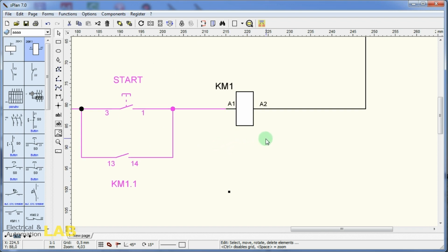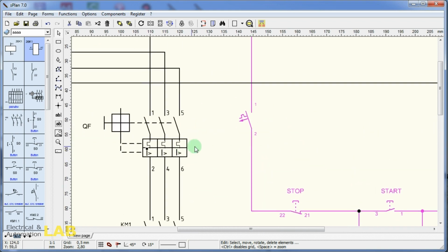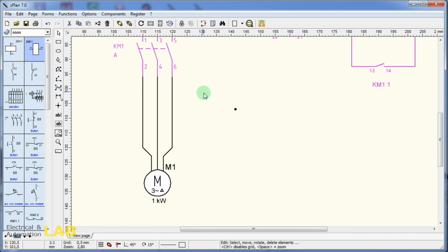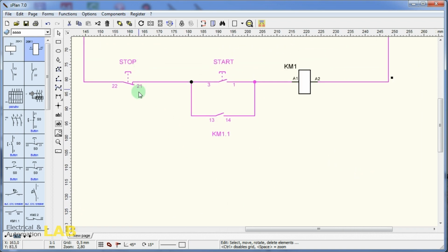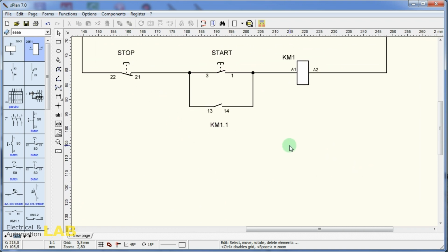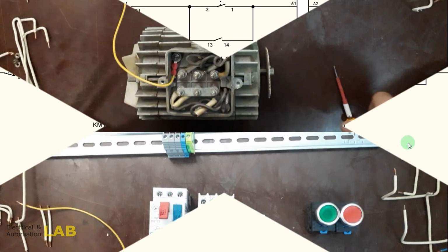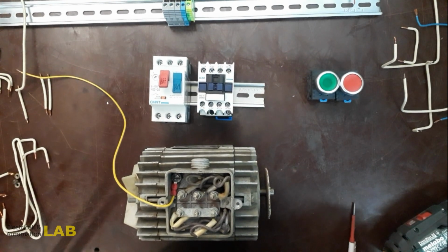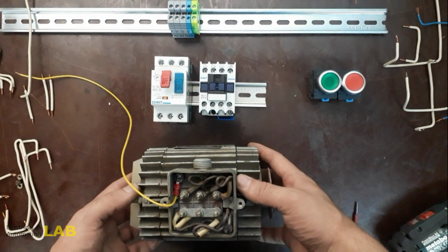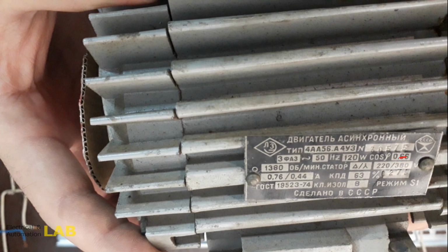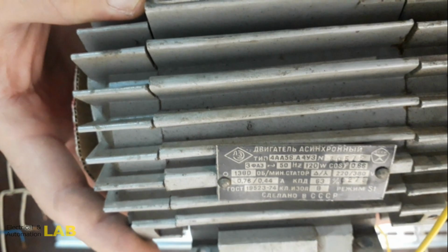The inclusion of KM1 leads to the inclusion of the electric motor. The motor will stay on until the coil supply circuit is interrupted. We break the power circuit with the stop button, and the electric motor stops. We have an electric motor and these are the specifications. The network voltage is 380, so we need to focus on the values after the fraction.